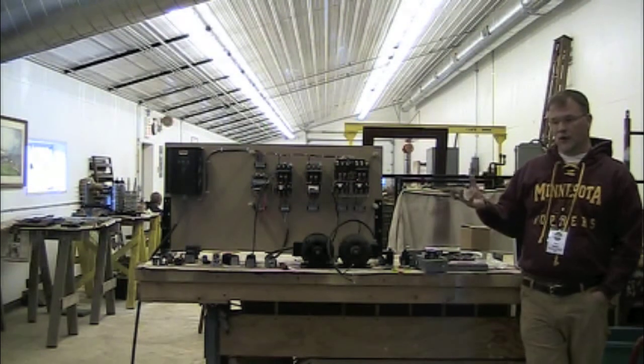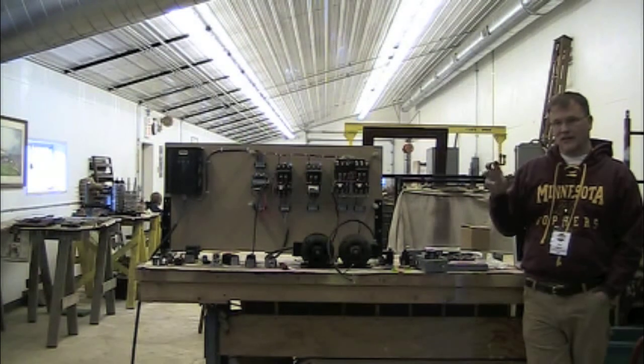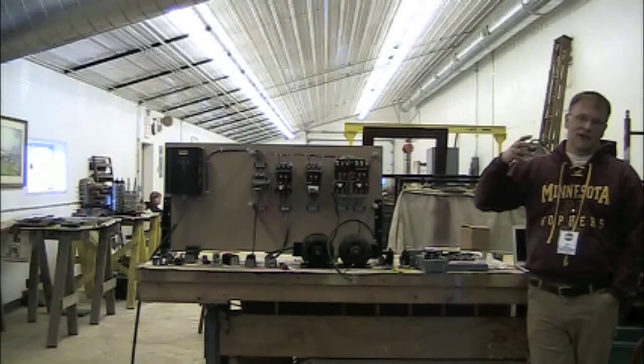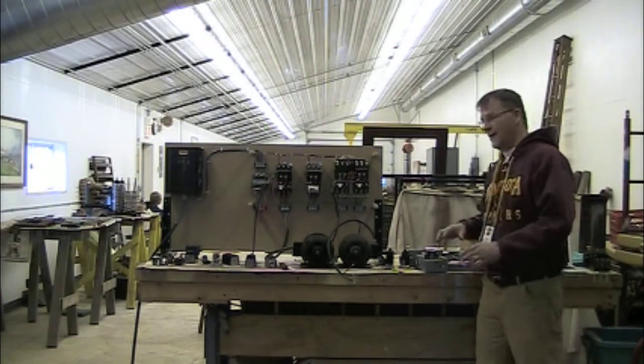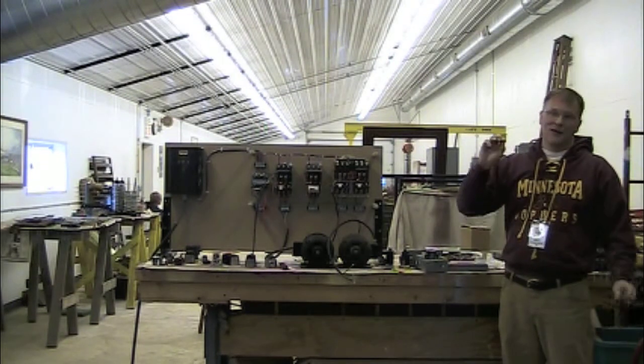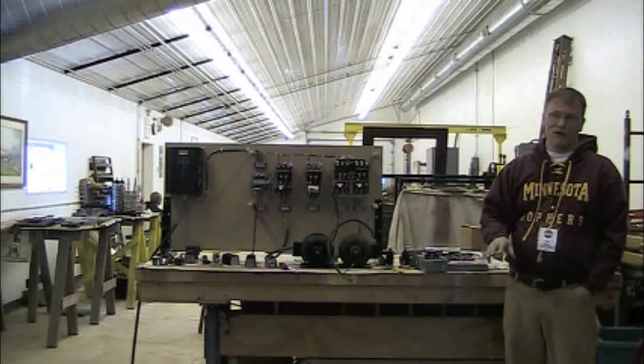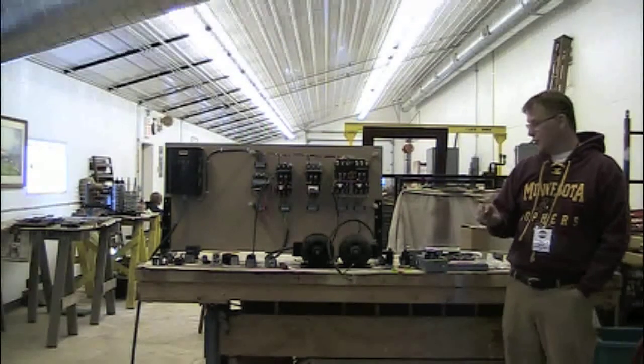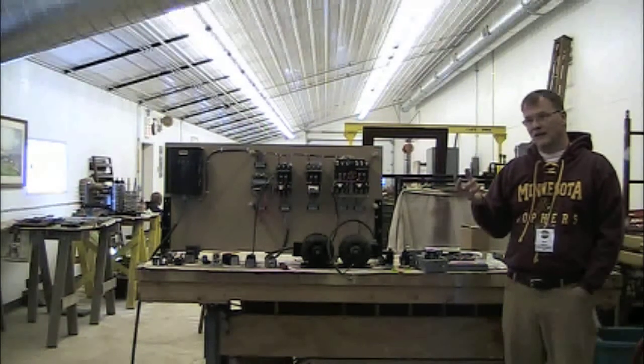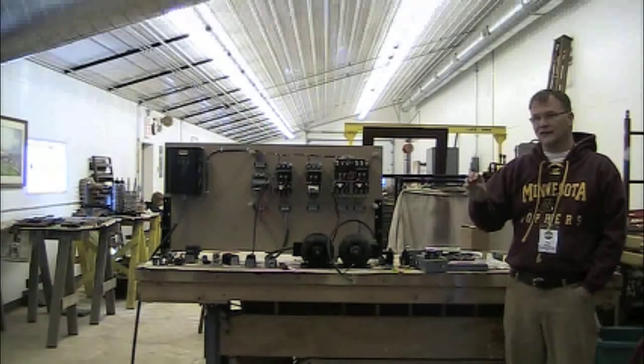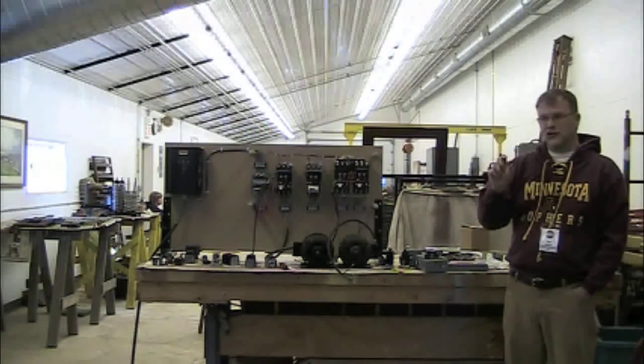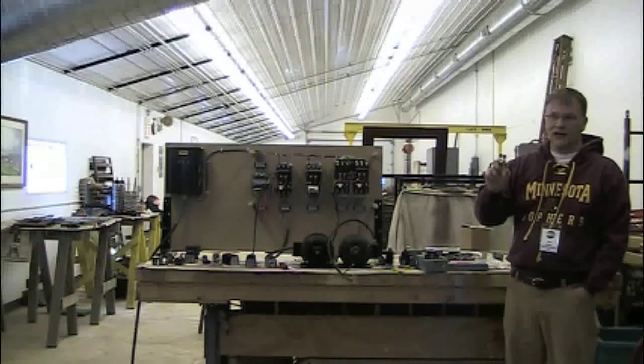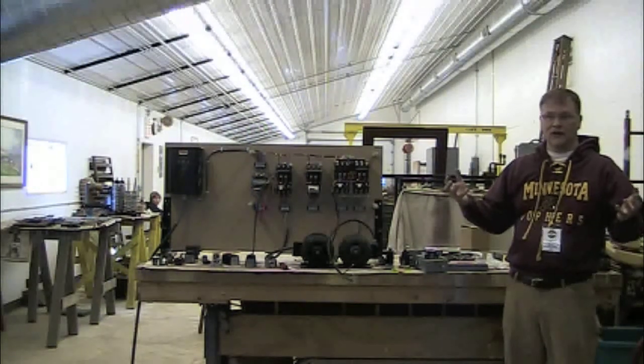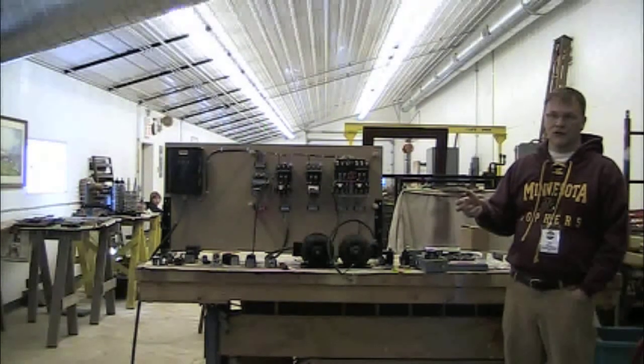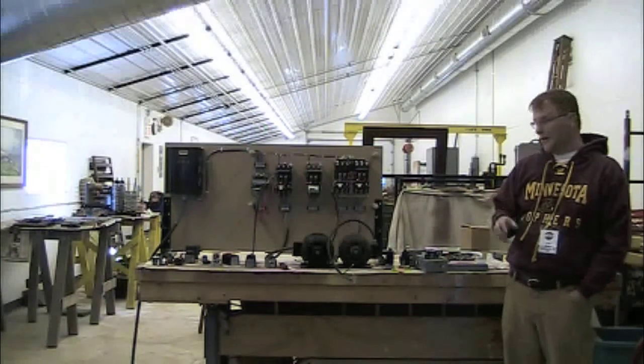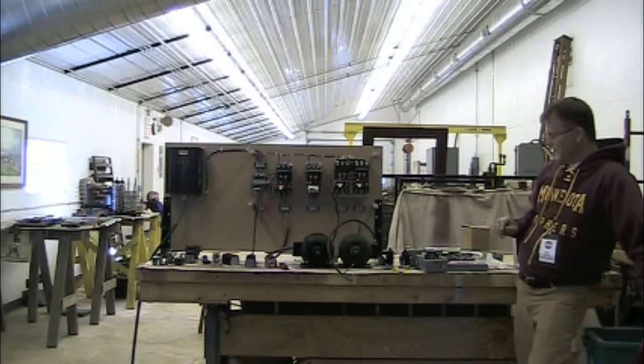And the design of most motor starter overload blocks is so that they mimic the characteristics of a motor. In Article 430, which is for motors, there's a clear distinction between what you're doing for your circuit protection and what you're doing for overload and overcurrent protection on your motor. The problem is you can get dual element fuses that are well tuned to the characteristics of a motor. They have really short interrupt capacity for short circuit, but they can run for large numbers of seconds at moderate overload without tripping. But they're really expensive to replace.